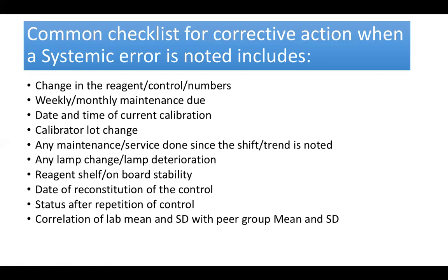Some change in the lot of calibrator. You are reconstituting some calibrator. It is not reconstituted properly. Or some maintenance service, or some lamp change is there, or the lamp is deteriorating, so it is affecting all your results.